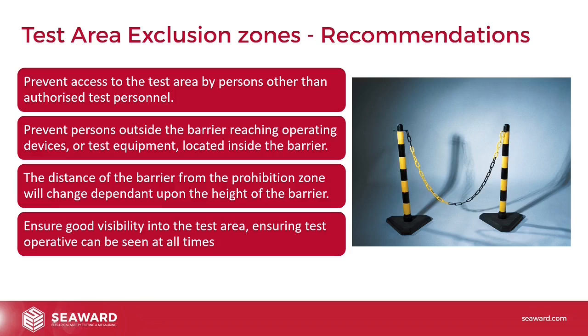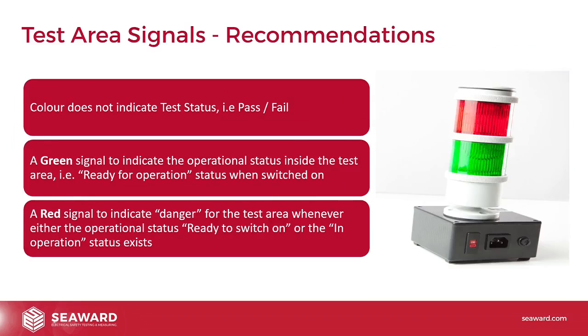We need to ensure really good visibility into the test area, ensuring the test operative can be seen at all times. So you might be tempted to build a big wooden box and entirely enclose your test area. It's not advised. The recommendations are very clear that you ensure good visibility in the test area. All kinds of standards have this, that you shouldn't work alone anyway, but we don't want a situation where the operator gets into some difficulty and no one can see him. So ensure good visibility into the test area at all times.